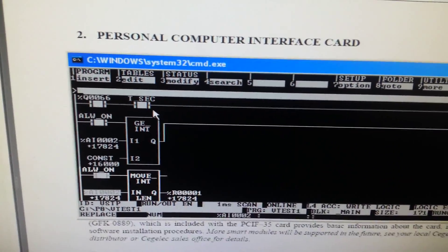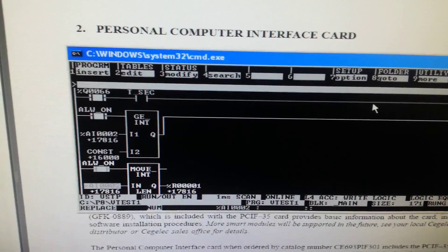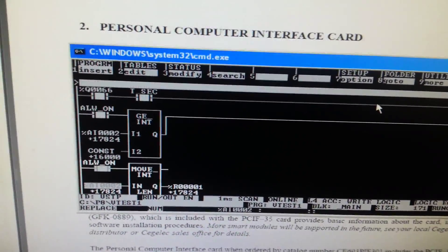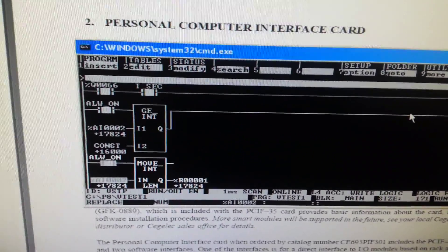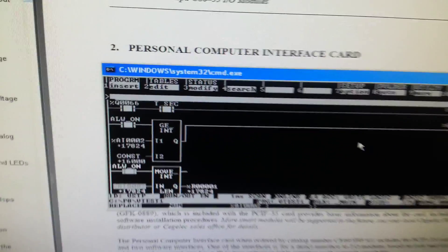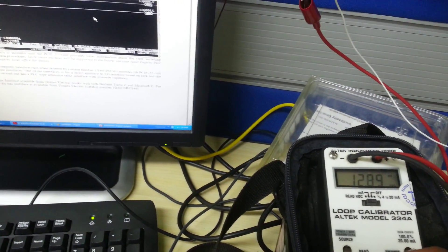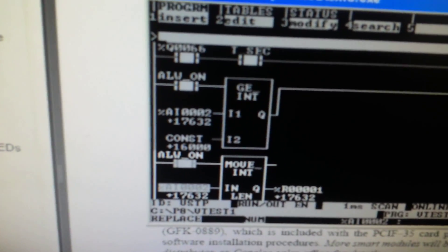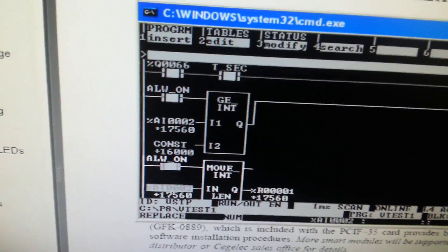Q 00066 is energized with blinking in series with the TSEC, which is a pulse blinking contact. Q 00066 blinks when the current is above 12 milliamps — that is, when AI 002 is above 16,000.